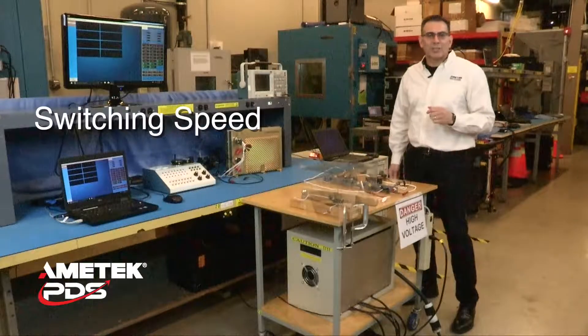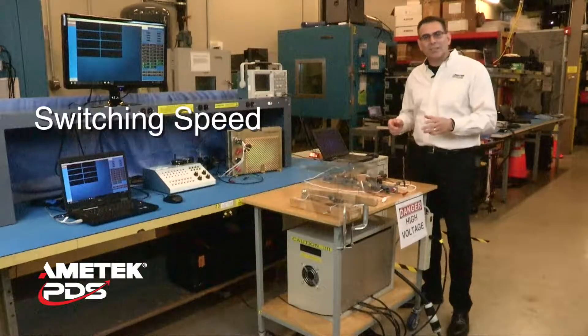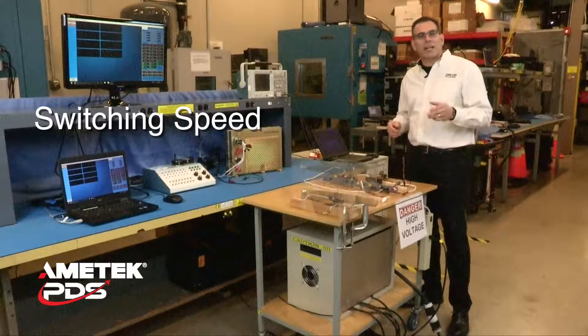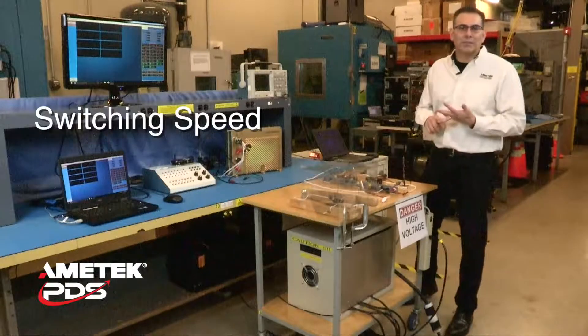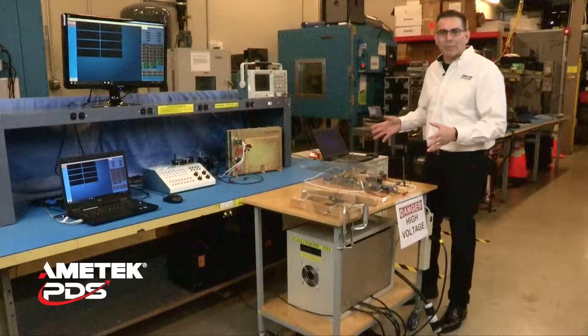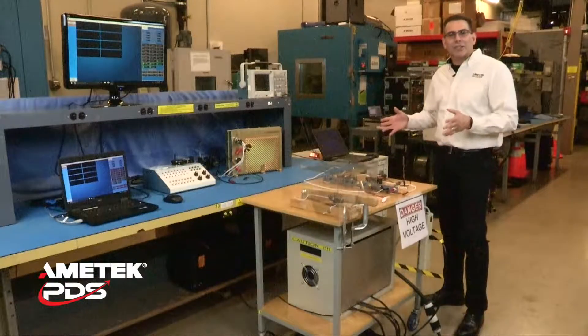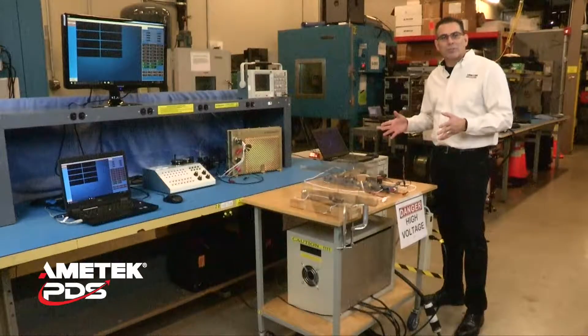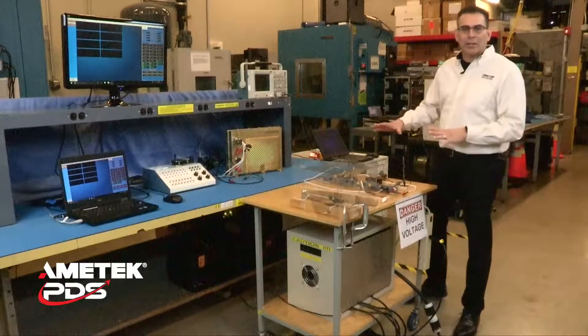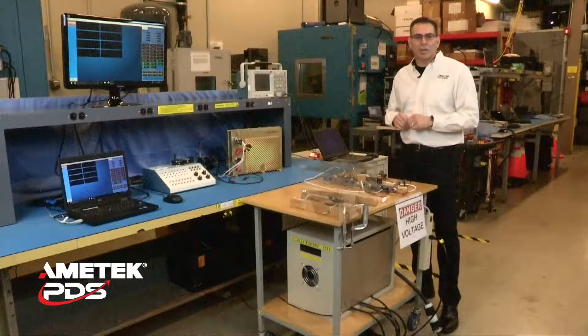Today we're going to do a quick demonstration that shows the speed advantages of solid state technology and the benefits it provides in terms of minimizing collateral damage to both the wire bundle and the aircraft. To do this, we've constructed a small experiment where we're going to compare the reaction of a standard MS3302 circuit breaker to an Ametek solid state power controller when a parallel arc fault occurs on its load line.